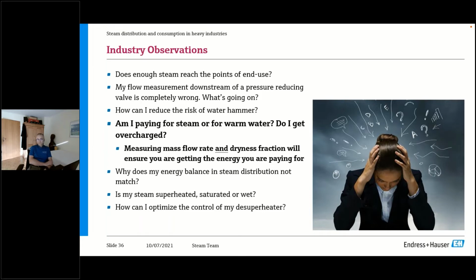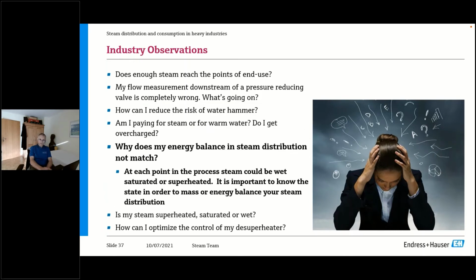Then are you paying for steam or for water? Do you get overcharged? Again, measuring mass flow and the dryness fraction will ensure you're getting the energy you're paying for. So this is also very important. And you get proof. What are you getting really? And then why does your main energy balance in the steam distribution not match? A very common problem is that people are using older meters and those don't come with the compensation of the dryness fraction. This is very often the problem. And if you don't know the dryness fraction, you don't know really the energy that is contained in your wet steam. This is very often the main problem that I've seen in their system.